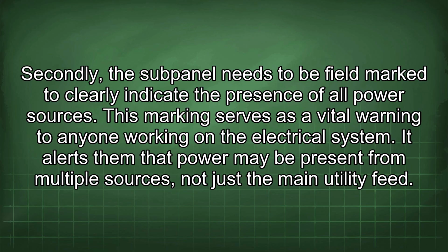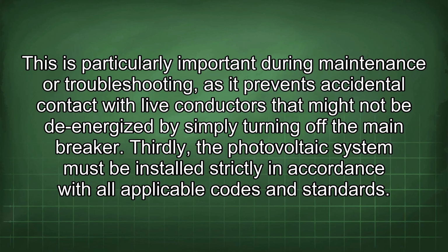Secondly, the subpanel needs to be field marked to clearly indicate the presence of all power sources. This marking serves as a vital warning to anyone working on the electrical system. It alerts them that power may be present from multiple sources, not just the main utility feed. This is particularly important during maintenance or troubleshooting, as it prevents accidental contact with live conductors that might not be de-energized by simply turning off the main breaker.